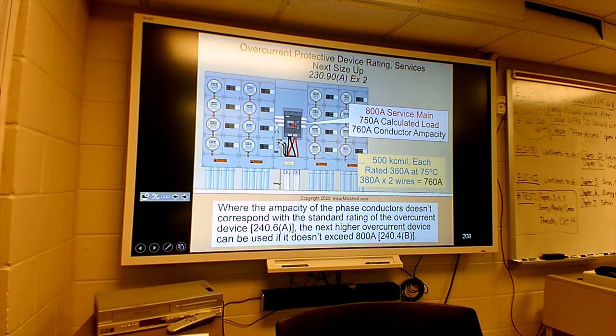It says here, where the amp rating of the phase conductors does not correspond with a standard rating of overcurrent device, they don't make a 760 amp disconnect or breaker, the next higher overcurrent device can be used if it doesn't exceed 800 amps. And that comes from Article 240.4. So you can go to the next higher size breaker. You can.